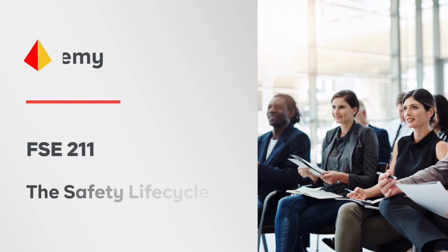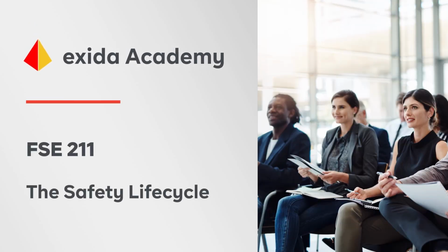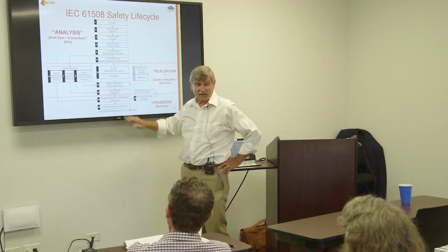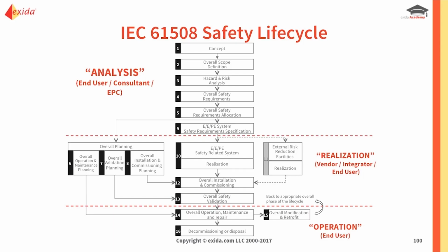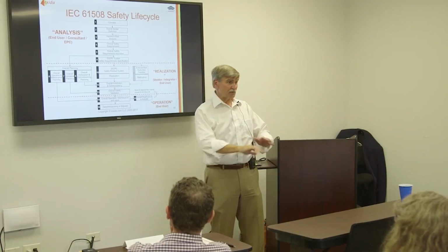That's a safety life cycle drawing from 61508. As you can see, it's a bespoke system. It goes all the way from scope definition to decommissioning. It's really meant to be an entire life cycle. And one of the reasons many members of the committee were so adamant is because they found many cases where designs were done really cleanly and operation, maintenance, and repair was done very poorly.